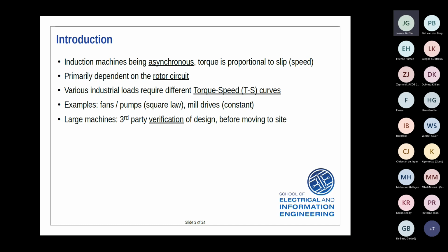As I've said already, induction machines being asynchronous, the torque is proportional to the slip. We'll look at that briefly in some various torque speed curves in a moment, and it's primarily dependent on the rotor circuit, as you all know. The rotor circuit is what shapes the torque speed curve - single cage, double cage, etc. - and that's done to satisfy various industrial loads which require these different torque speed curves. So, for example, fans and pumps we want a square law torque speed curve, or a mill drive for example, where we want relatively constant torque. We can achieve those in our motor design, primarily from the design of the rotor circuit.